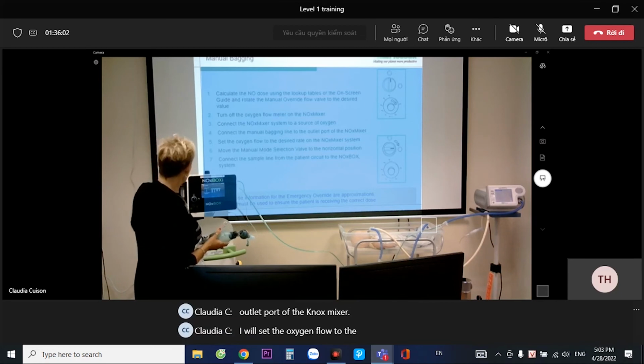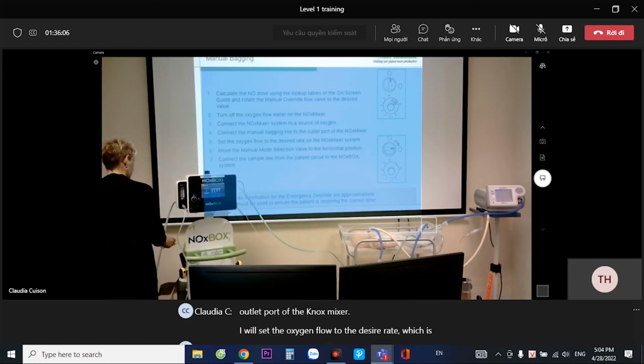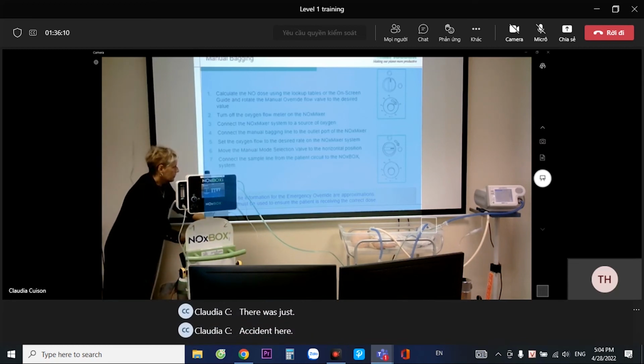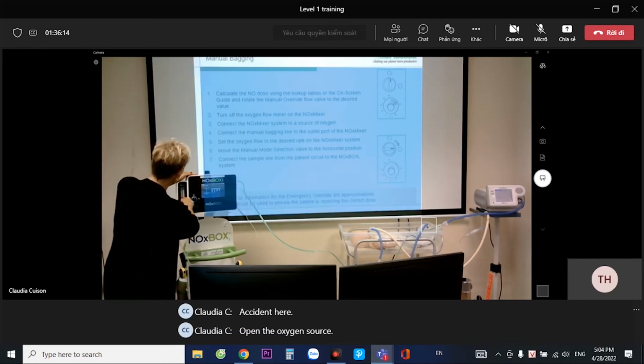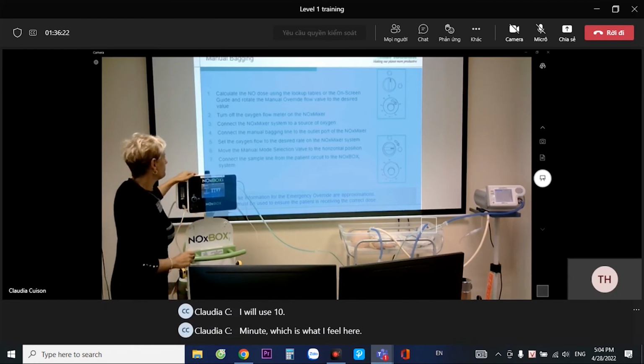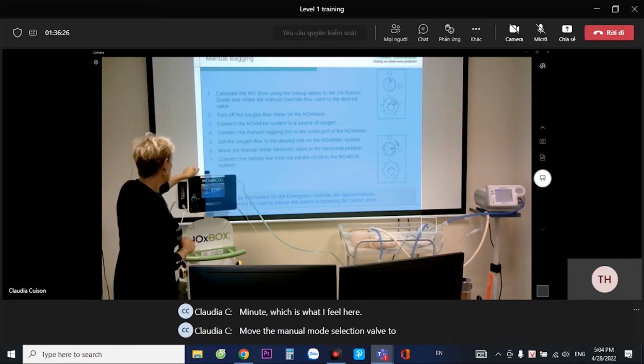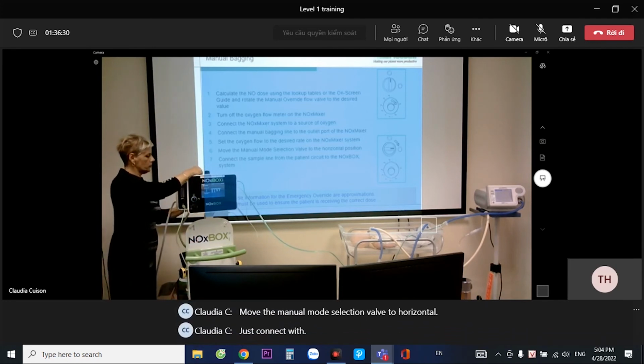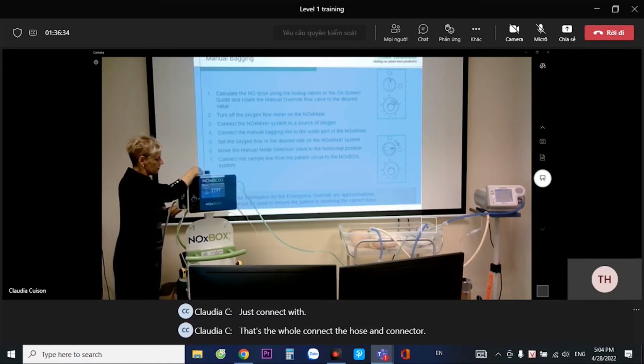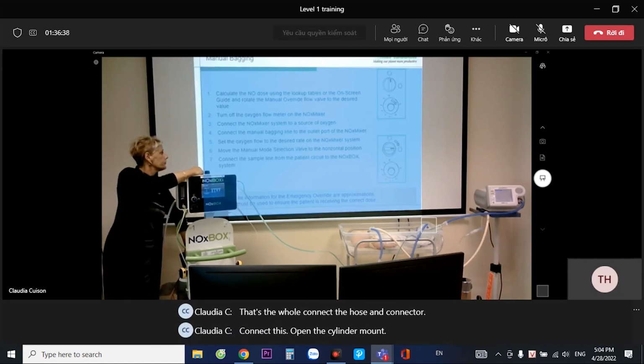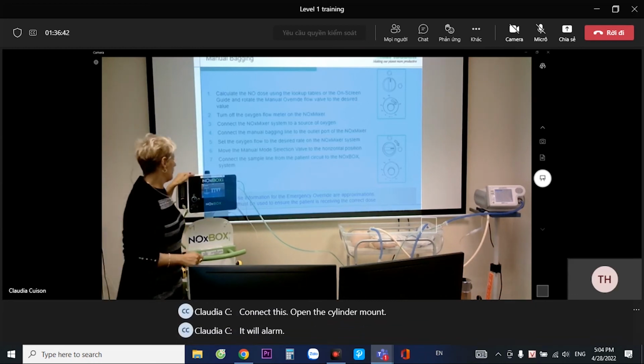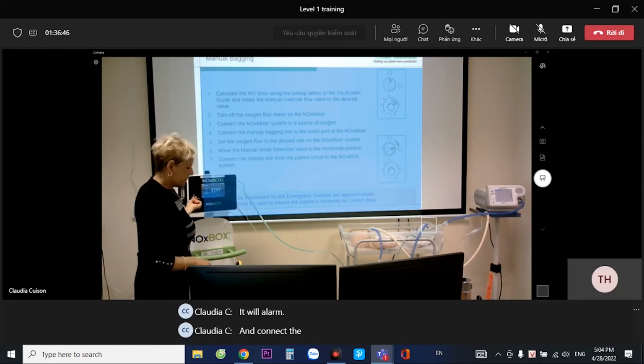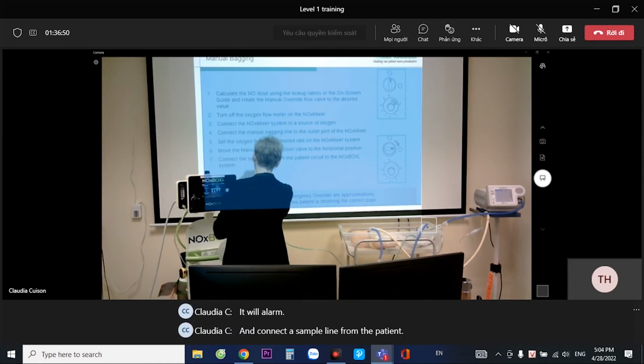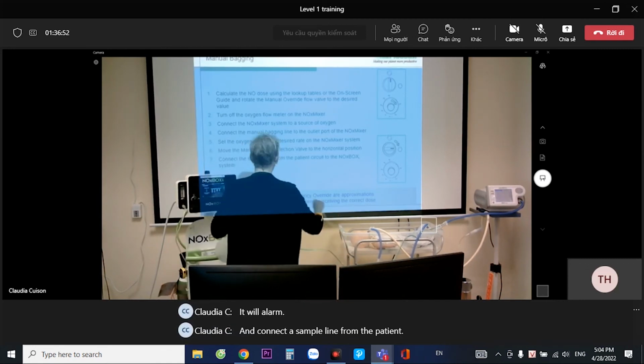I will set the oxygen flow to the desired rate, which is normally, let me just open the oxygen here. Open the oxygen source. I will use 10 liters per minute, which is what I put here. Move the manual mode selection valve to horizontal. You just connect this, first of all, connect the hose and open the cylinder valve. It will alarm, and connect a sample line from the patient. Connect the sample line from the patient circuit to the NOx box system.